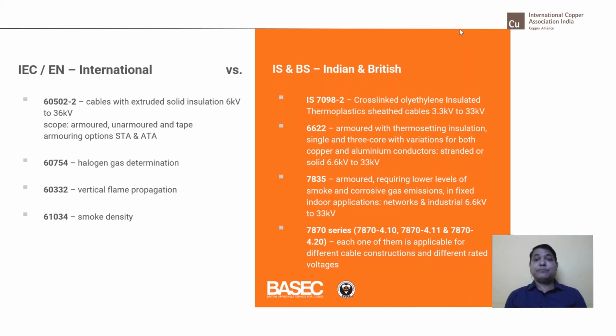It is one standard. When it comes to British standards, the 3 kV voltage grade goes under the low voltage standard itself. But 6.6 kV to 33 kV is the medium voltage standard. In British standards, there are two standards separately. BS 6622 is for PVC bedding and sheath cable, whereas BS 7835 is for low smoke zero halogen sheath cables, which are normally used within buildings where safety is very important or specified.